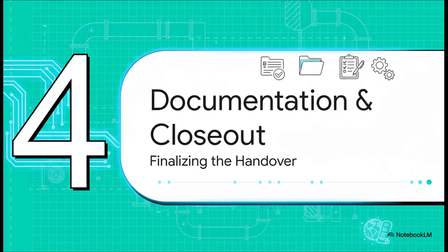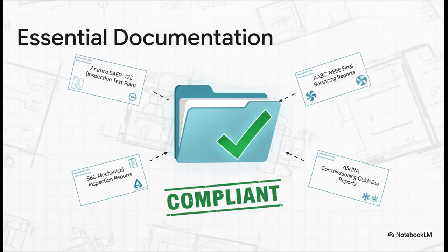So the system is installed, it's tested, it's balanced. Awesome. But you are not done. Not by a long shot. Now we've got to get through the final and, honestly, one of the most critical phases: documentation and closeout. And here's the deal. You could have the most efficient, perfectly running system on the planet, but if you don't have the paperwork to prove it, it basically doesn't count. You need to assemble a whole package of proof: the inspection plans, the official reports, the certified balancing data, all of it. This is the paper trail that proves you did your job right.